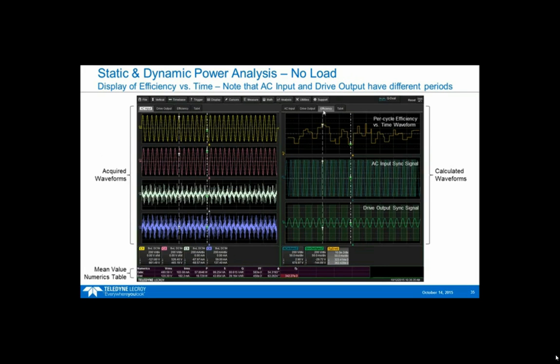I've just chosen a different tab on the right. I've labeled that efficiency, and I've clicked on this value right here in this mean power table. If I click on that value, it creates a waveform. What we're showing here is a waveform of efficiency over time. It's what we call the per cycle waveform, and it has one value every time there's a cycle.